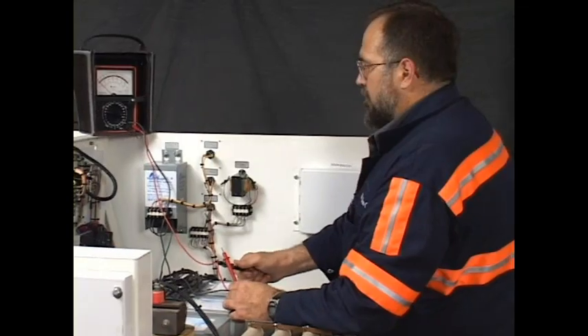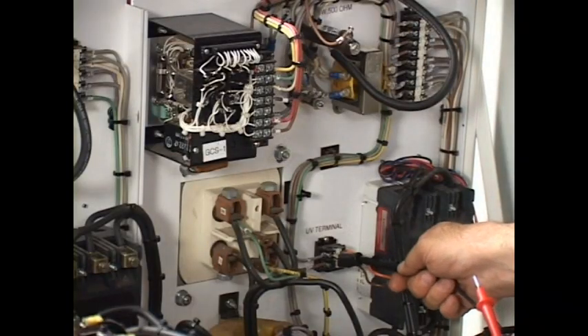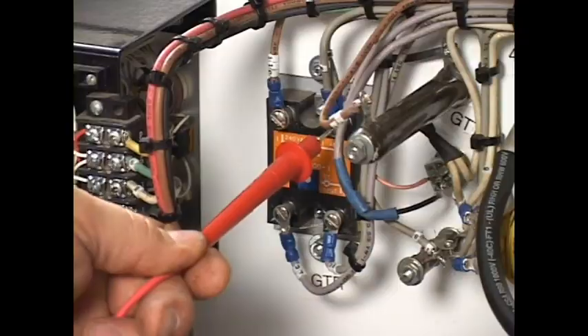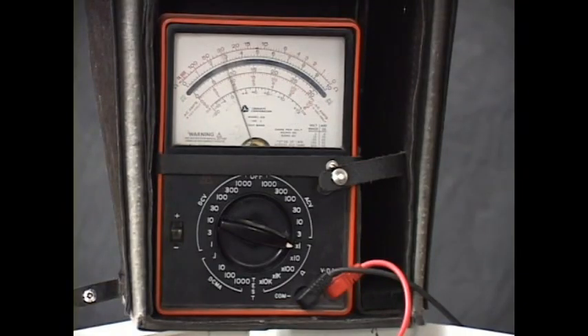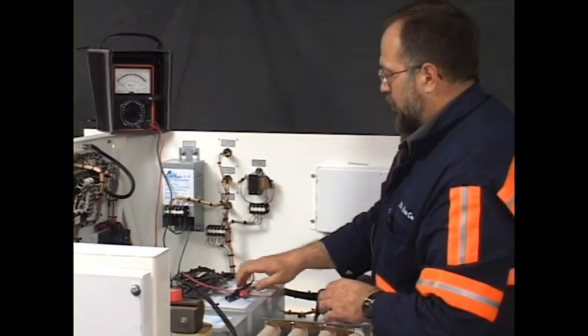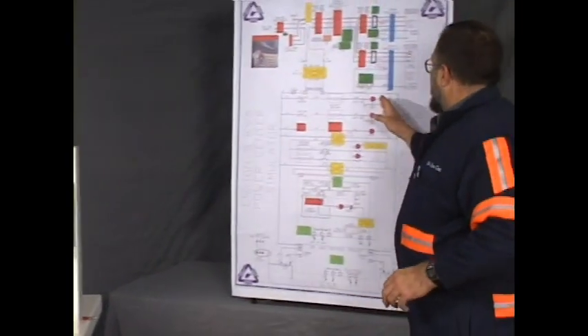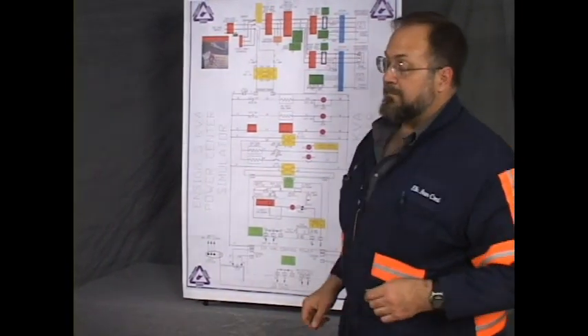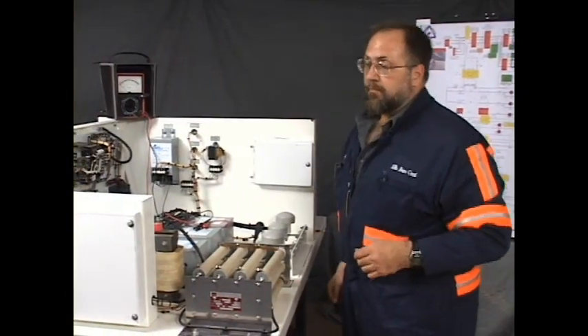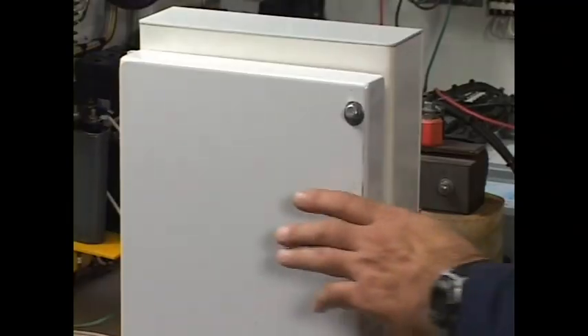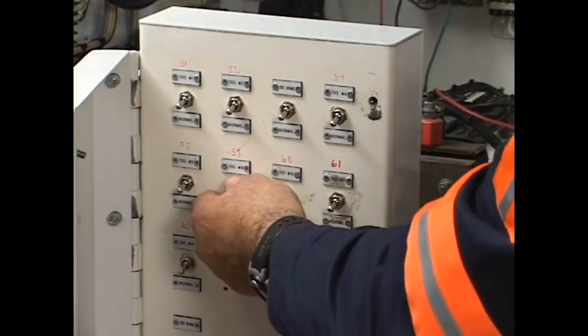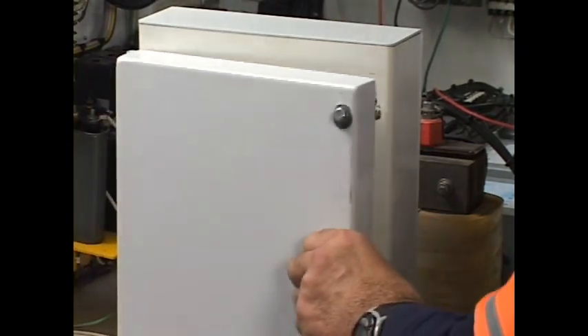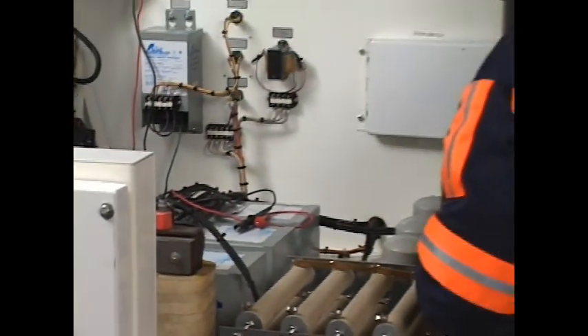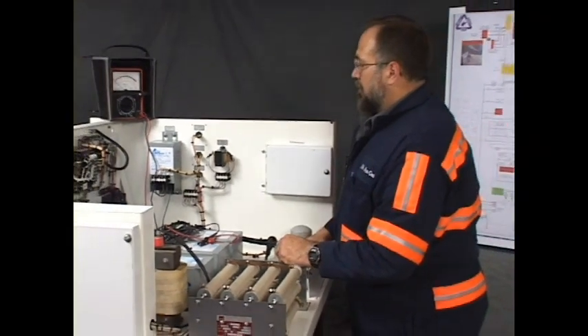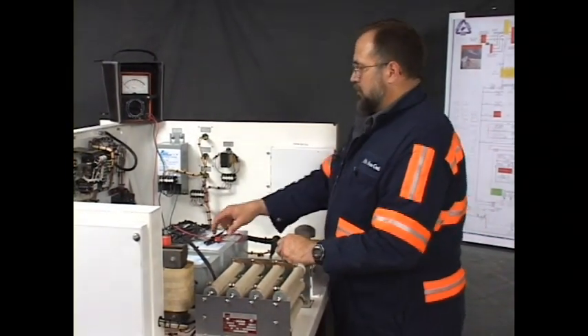Now the other side of that circuit is wire number 8. As I said earlier, for the state examination, there are no problems involving the return wire, wire number 8. And in fact, you may encounter those in real life. Now we're going to install the problem on the power center. I'm going to open the test panel and close switch 59, put problem 59 on the board. By doing that, we've changed the wiring.